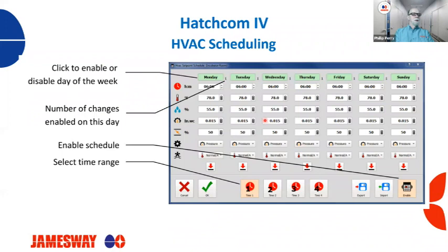Let's say your chick holding room is only used, you only hatch 4 times a week, so you only hold chicks in there for 4 days. And so you could turn the heat off or make different settings so that there's no demand for energy on that room when not in use. Another room, if you have it on our Guardian system: service room, washroom, storage, hallways.